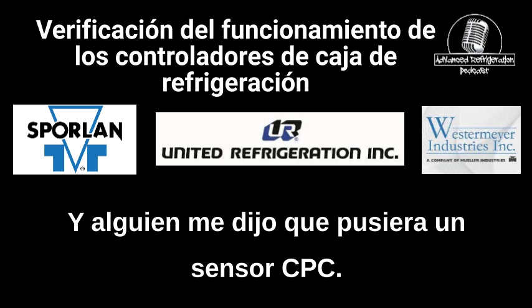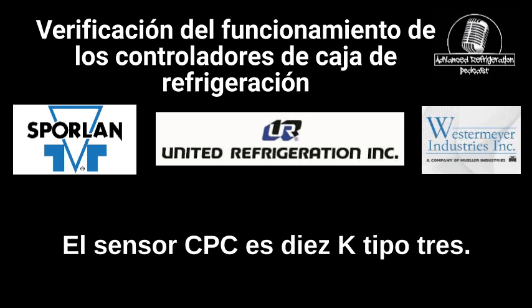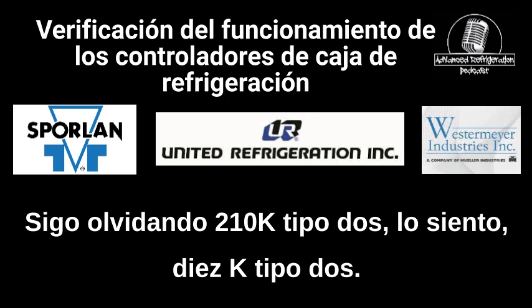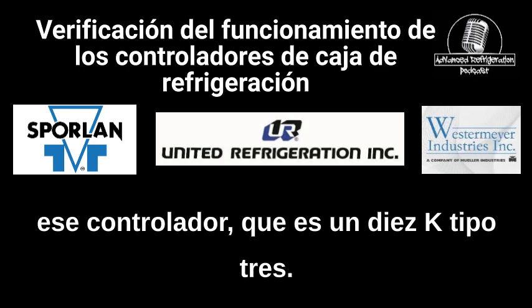And someone told me to put a CPC sensor in, and you have to watch, because the regular CPC sensor is a 10K type 2. Sorry, I keep forgetting. And then you have the black sensor, which goes to that controller, which is a 10K type 3.